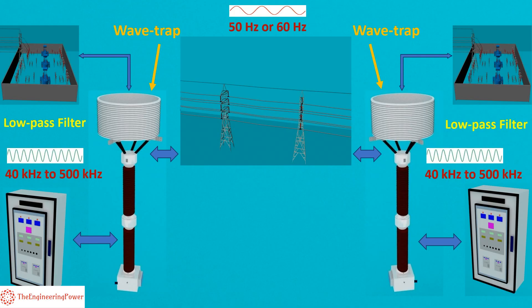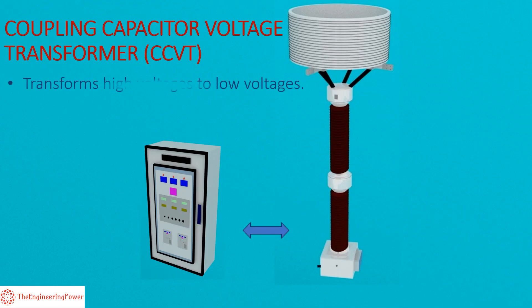A wave trap is basically a low-pass filter which passes the low frequency power voltage and stops or traps the high frequency PLCC signals from entering into substation yard, therefore known as wave trap. So CVT combined with PLCC equipment and wave trap makes the CCVT. CCVT performs two functions: it transforms high voltages to low voltages for protection and metering purposes just like CVT and PT, and secondly it couples PLCC equipment with high voltage power lines for telecommunication and teleprotection purposes. Hopefully the difference between PT, CVT, and CCVT is clarified in this video. Keep in touch for more such videos.